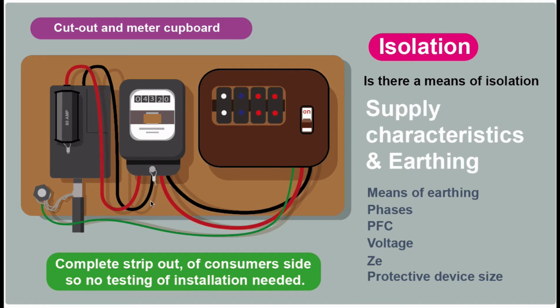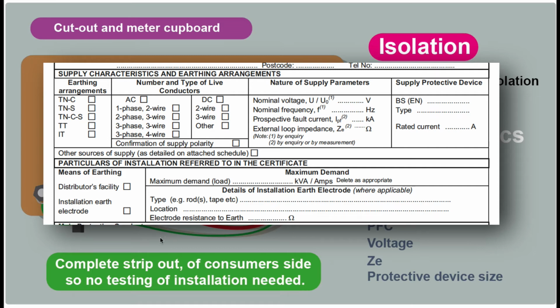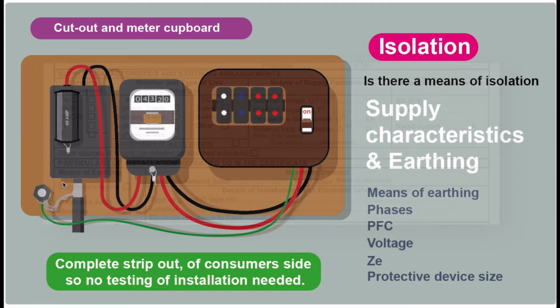But we can test if you've got an earth coming into the property, the supply characteristics and earthing. We can check these. We can check if we've got the prospective fault current. We can check the ZE, because these are the things that are beyond our control. If we've got a bad ZE reading, we're going to have to call the DNO to come and look at that.